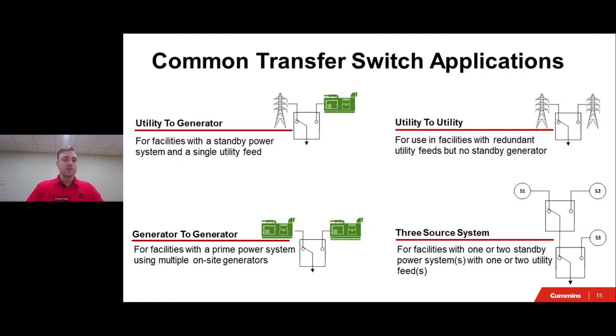So next up, when looking at how transfer switches work, it is also important to understand what kind of applications your transfer switch is going into, as well as where that transfer switch sits inside that application. So for starters, we're going to go top left and then bottom left and then so on and so forth on the right side. So we'll start off with utility to generator. This will be most applications that you all see. This is when you have a facility that relies on a normal source, usually being the utility, with a standby power system, usually being that generator, and the transfer switch transferring power between those two sources.